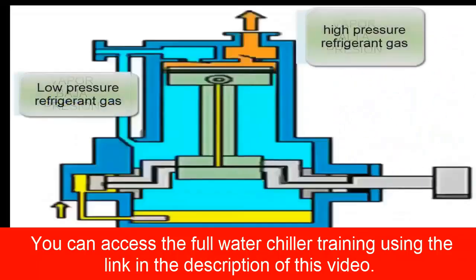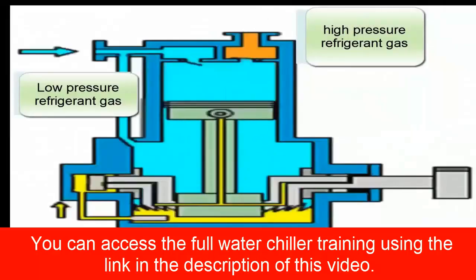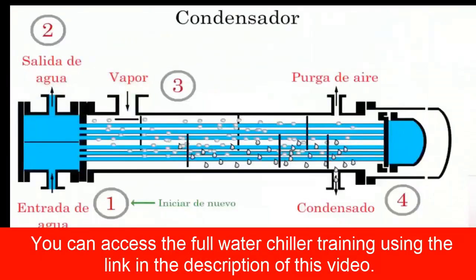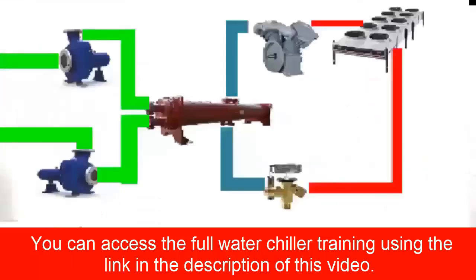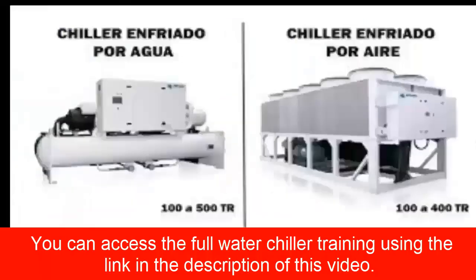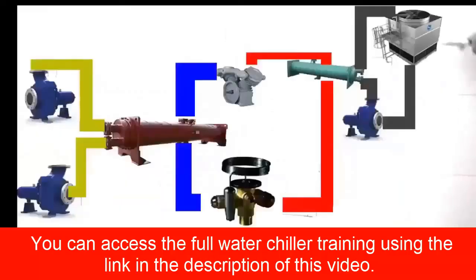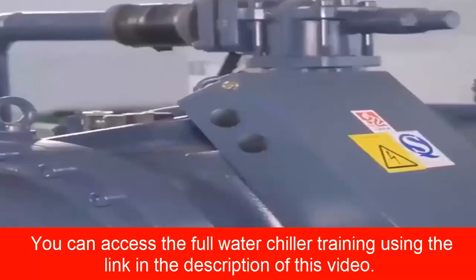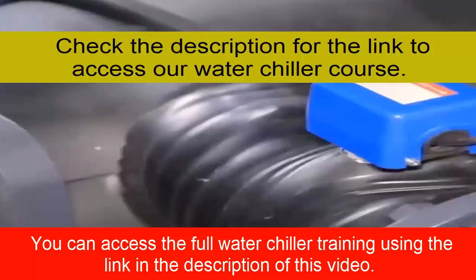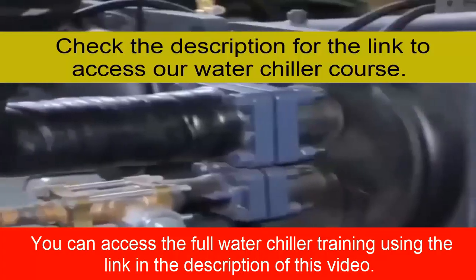Afterward, the vapor is drawn into the compressor, where it is compressed, increasing both its pressure and temperature, and then sent to the condenser. At this point, a fundamental process of the cycle occurs. The refrigerant must return to the liquid state. The simplest way to condense a substance is by increasing its pressure, because higher pressure forces the molecules closer together, facilitating the phase change from vapor to liquid. Therefore, the condenser requires two essential conditions: high pressure and cooling. When both are present, the refrigerant condenses quickly.